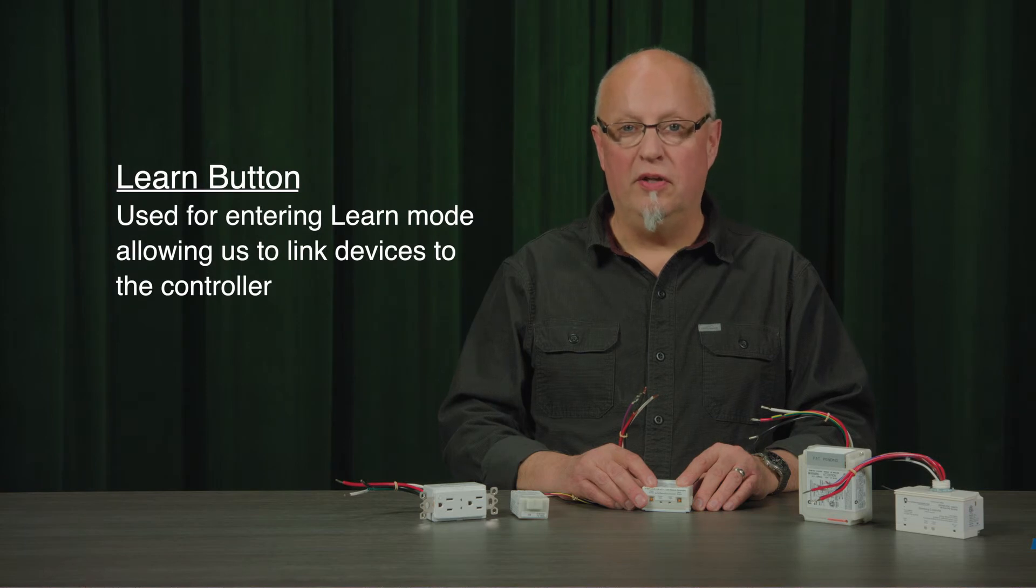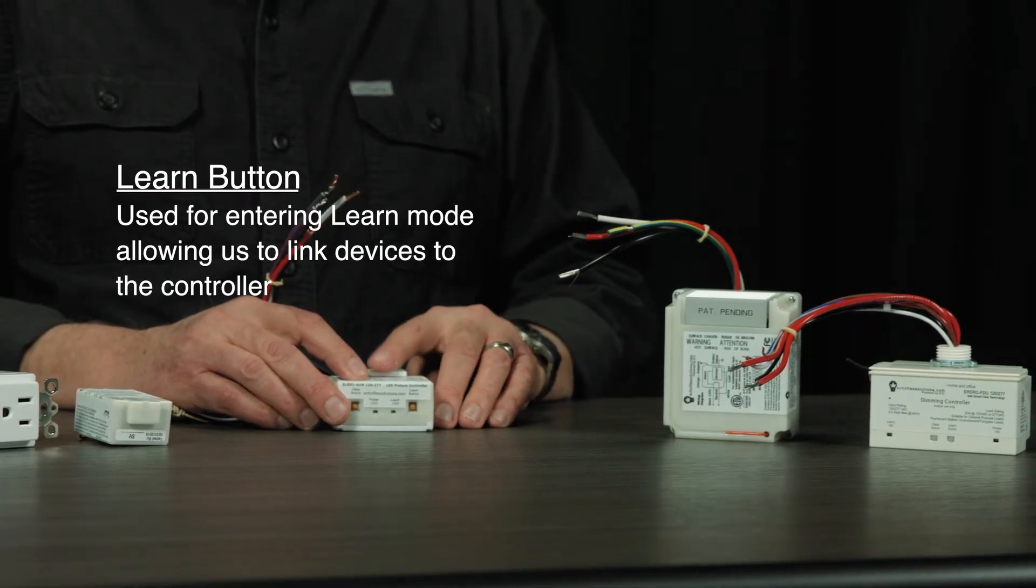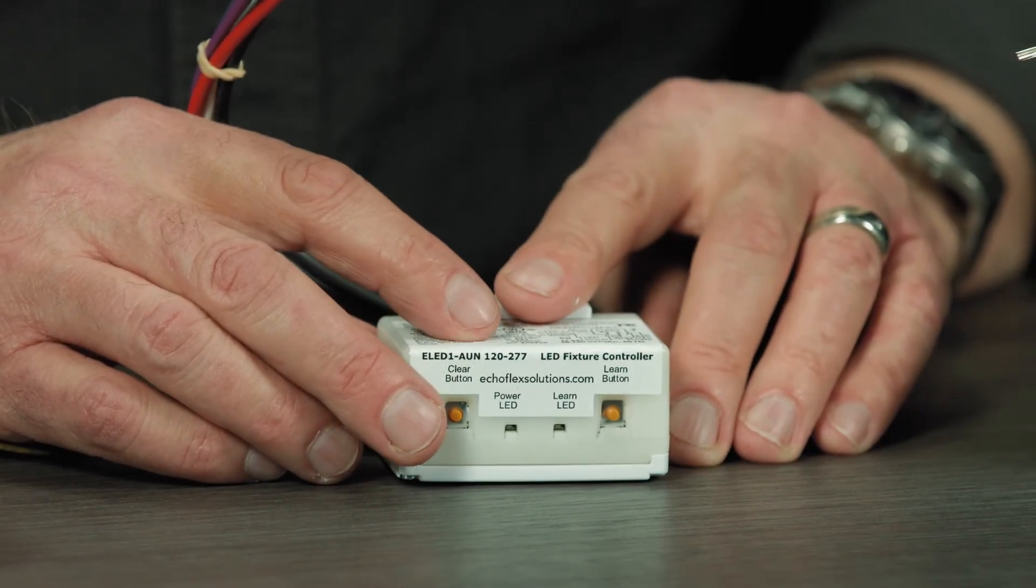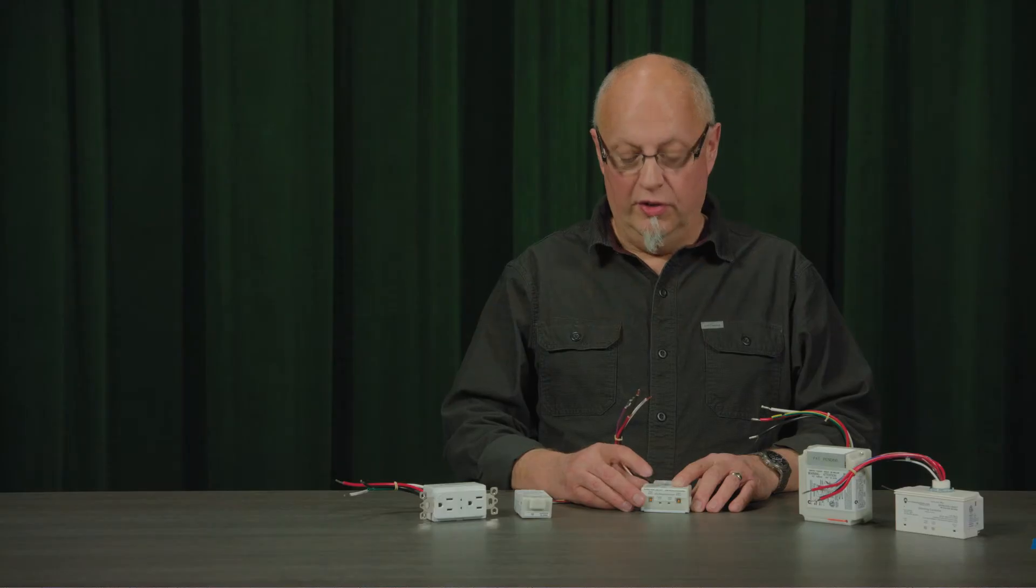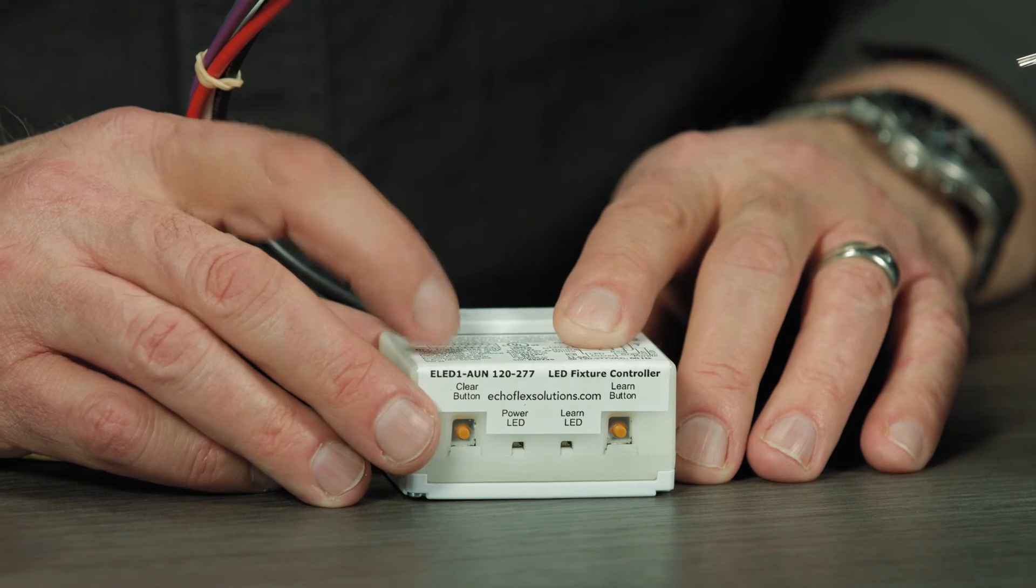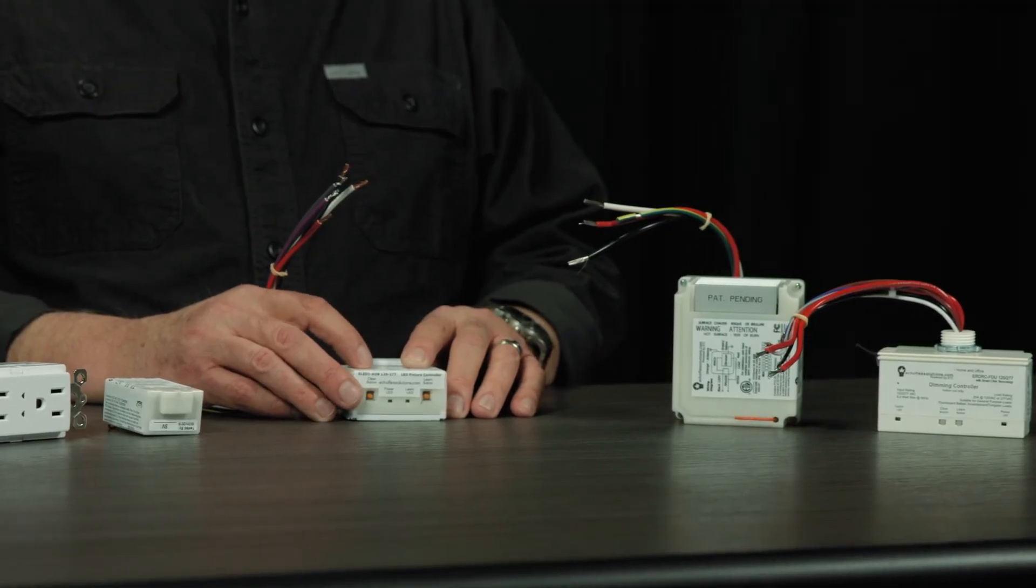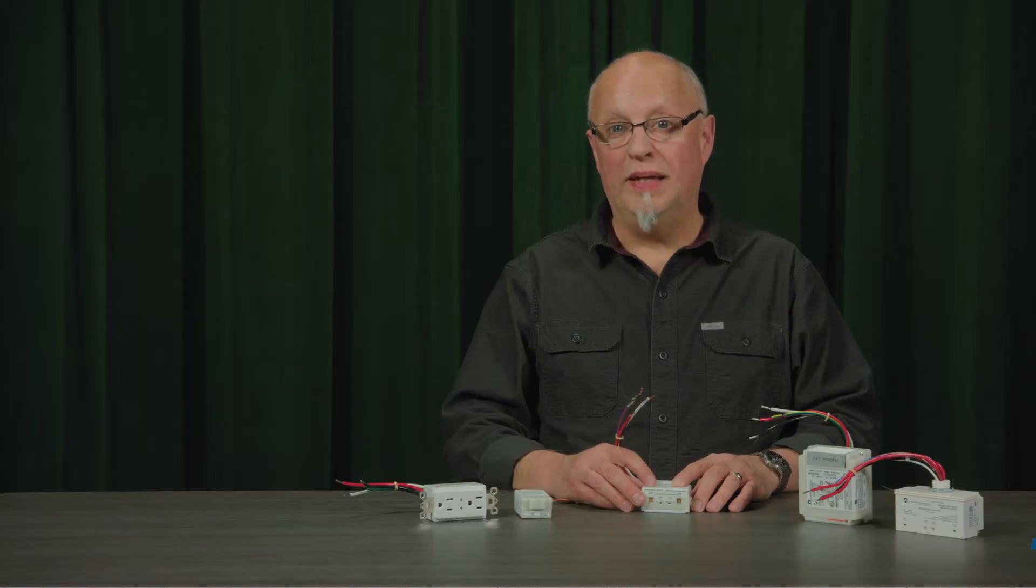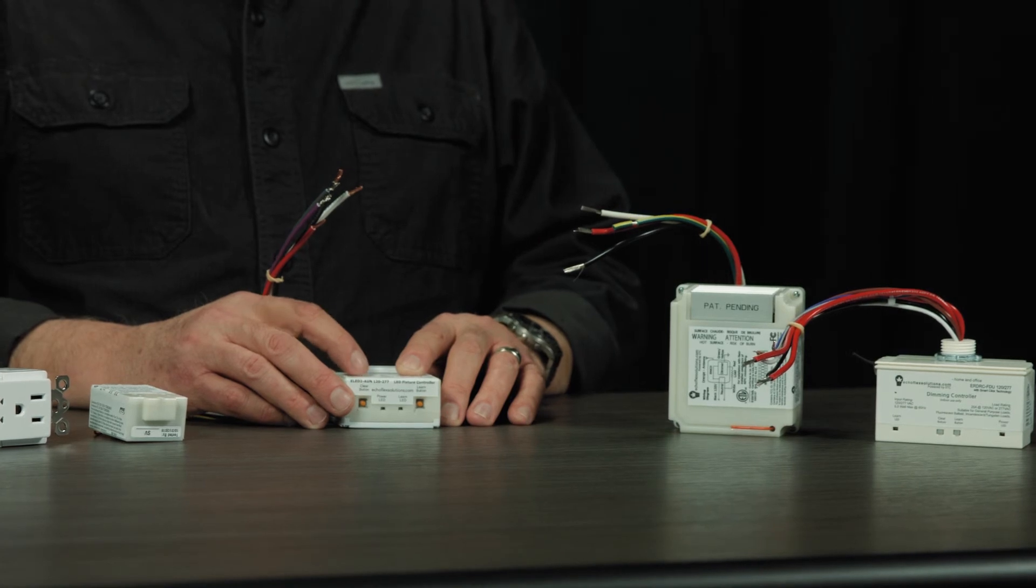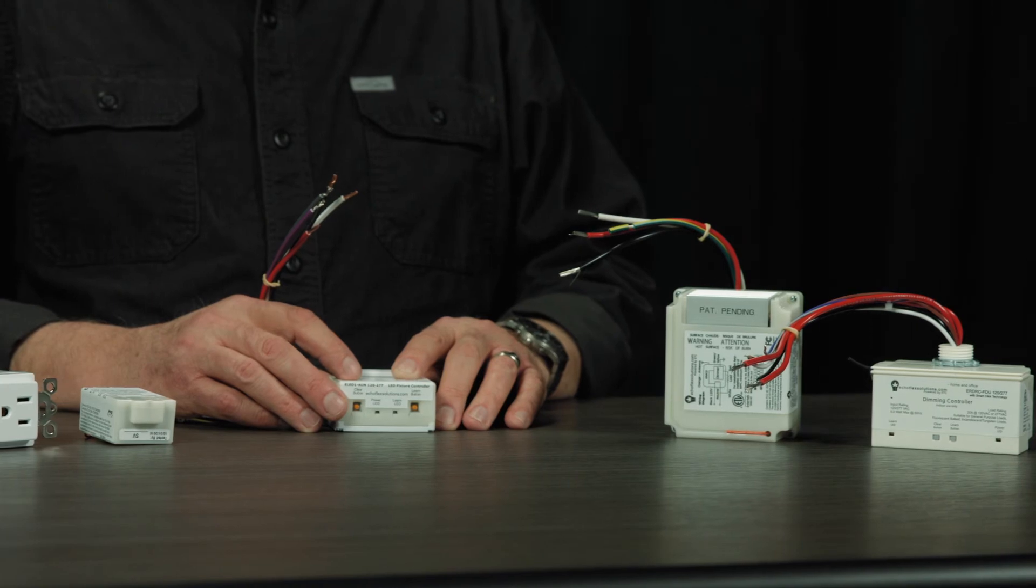So the learn button is what we use to link devices together. I need to put my controller into learn mode by pressing this button in. It's going to cycle its relay and raise and lower the lights. The learn LED will be on solid green. The red LED will be blinking at the same rate as the relay is blinking. After you've exited learn mode by pressing the learn button again, the red power LED will blink a pattern telling you what you have linked to the device and how many of that device you have linked. Check the install guides for more about these blink codes.